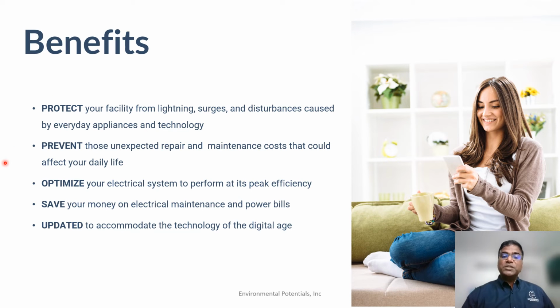So you will reduce the operating expense on these units, on your facility, by properly utilizing EP filters. And we increase the efficiency of the system by reducing the heat in the system, on the transformers, on the induction motors, on the wires, on the unit itself. Therefore, you consume less energy from the main. Basically, you just save money, capital investment, and also operating expenses in your facility by using EP filters.